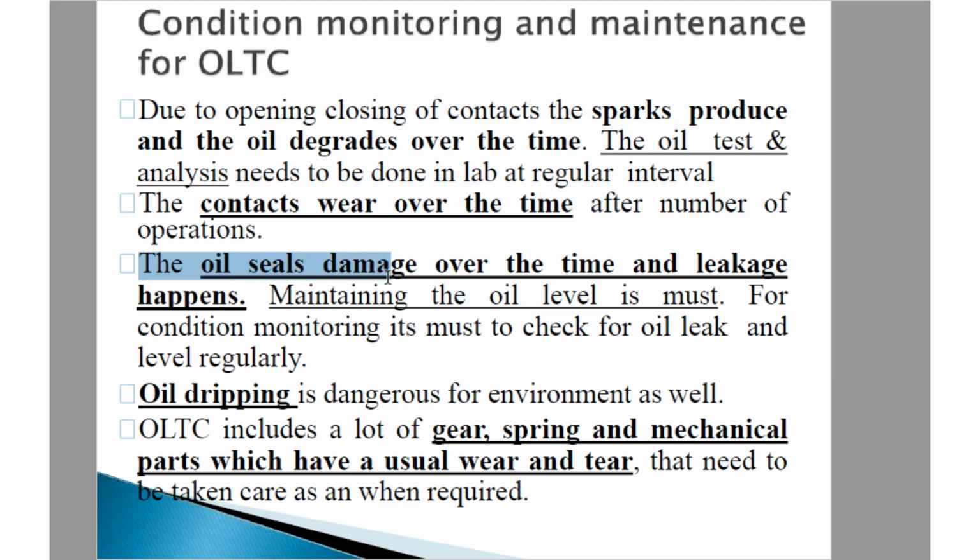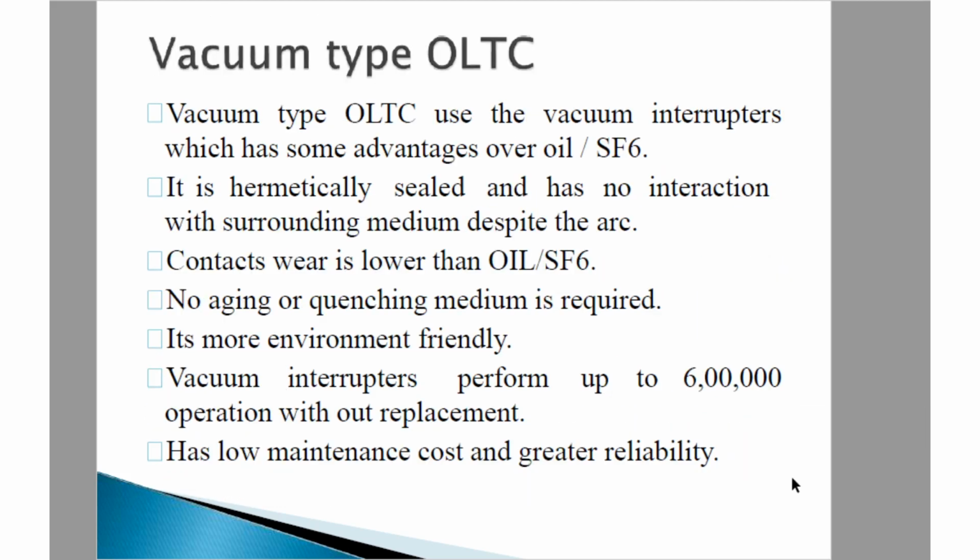The oil seals get damaged over time and leakage happens. Maintaining the oil level is a must. For condition monitoring, it is a must to check for oil leak and level regularly. Oil dripping is dangerous for the environment as well. So OLTC includes a lot of gears, springs and mechanical parts which have usual wear and tear that need to be taken care of as and when required.